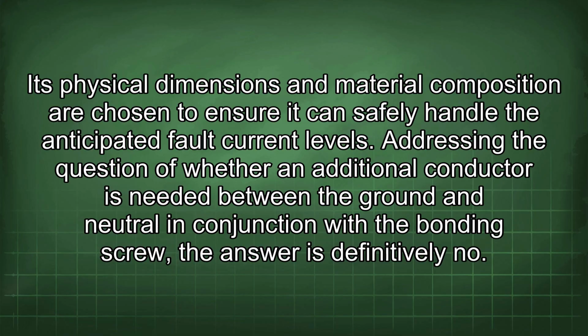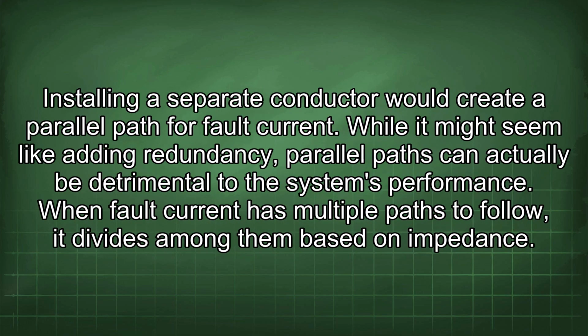Addressing the question of whether an additional conductor is needed between the ground and neutral in conjunction with the bonding screw, the answer is definitively no. Installing a separate conductor would create a parallel path for fault current. While it might seem like adding redundancy, parallel paths can actually be detrimental to the system's performance.